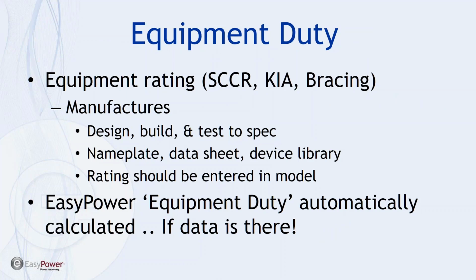As equipment is designed, built, and manufactured, the manufacturer is providing technical parameters, usually in the form of a data sheet or on a nameplate of the panel or the switchgear, the rating that he has tested or guarantees that equipment to work properly. And so consequently, that needs to be entered as we're doing the modeling in EasyPower. And once it's there, the tool will automatically verify whether or not the equipment's adequate to the task.